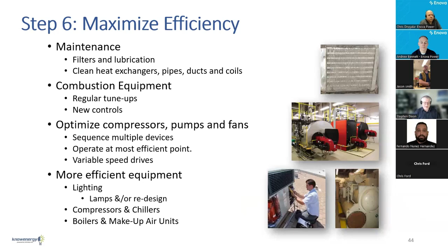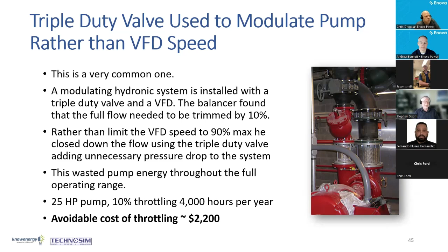I mean, how many times do we go out and look in a mechanical room, and here we see a circulating pump with what we call a triple duty valve, throttling it, right? Which means it's trimming the flow. Well, it turns out in this case, they had a variable speed drive available and powering this pump, but it was running at full speed. Ironically, a variable frequency or variable speed drive running at full speed will use marginally more power than that motor will without that drive, because there are drive electronics inefficiencies. So in this case, unthrottling that valve, and then using the drive to limit the flow, to balance the system: $2,200. So again, the operational side of it is so important.